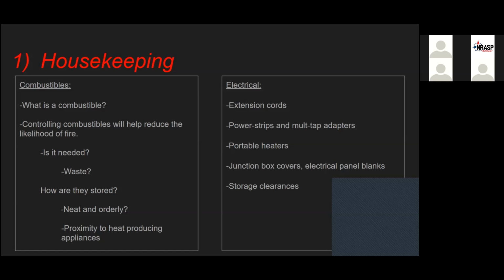And storage clearances in regard to electrical. The fire code says that you cannot have any storage within 36 inches to the front of the panel and any storage within 30 inches to the sides of the panel. And this primarily is for working space for us to come in if there's an event in your facility so that we can get to the panel and shut power off as we need to. But there is also an element of fire prevention. We have seen where a building's been struck by lightning and it actually ends up blowing out the panel and sending sparks through that room. So it's always a good idea to keep that panel clear for a multitude of reasons.